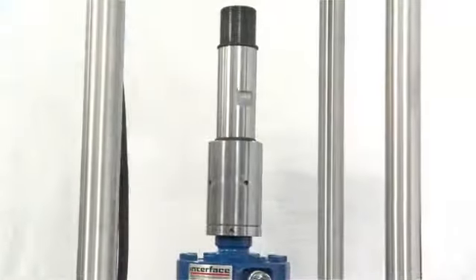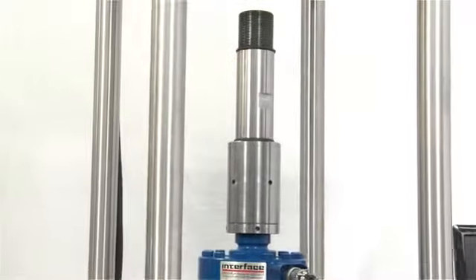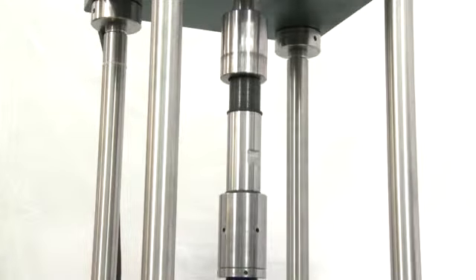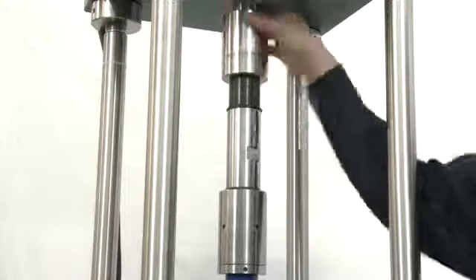With all load cells in place, we will want to exercise the load stack once or twice. This helps relax the load string and make sure that there aren't any problems in our completed setup.